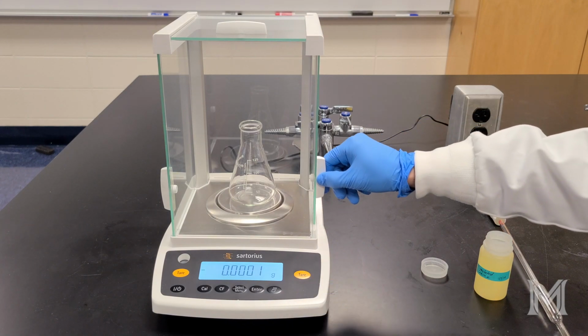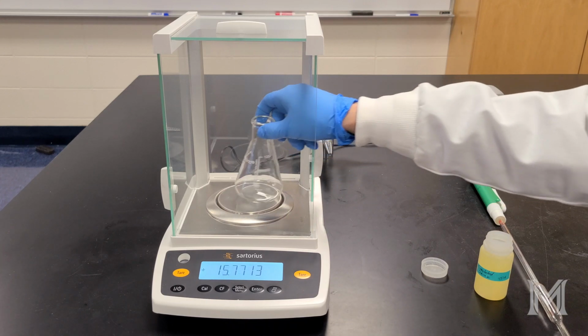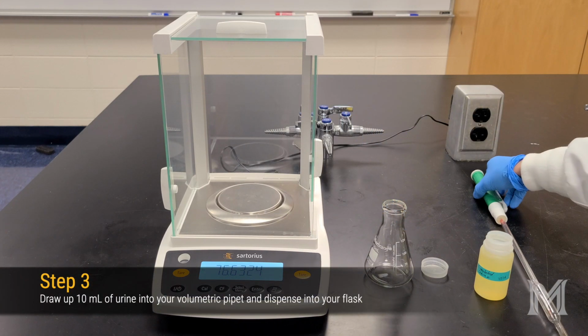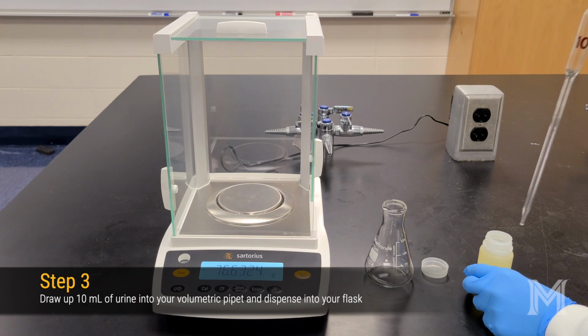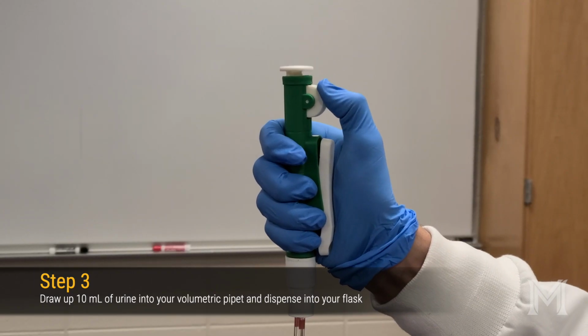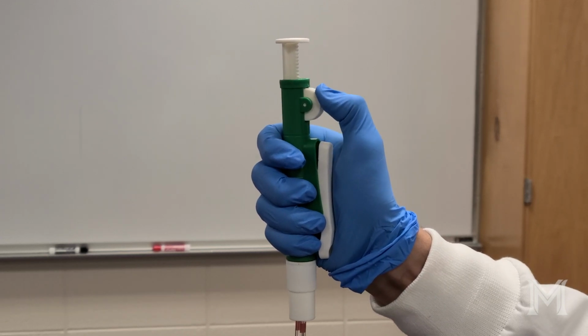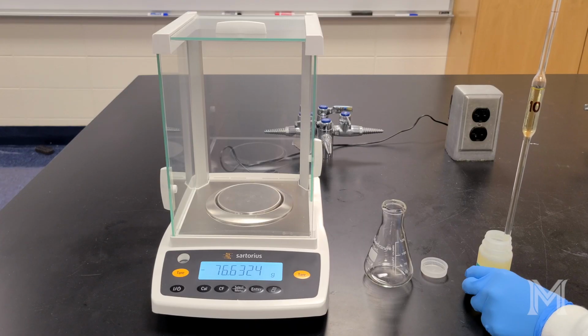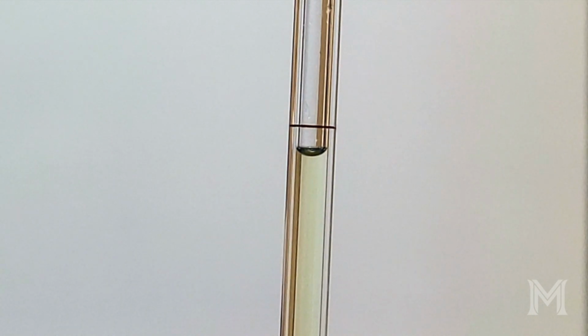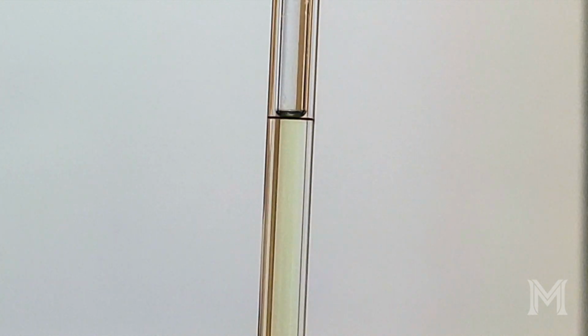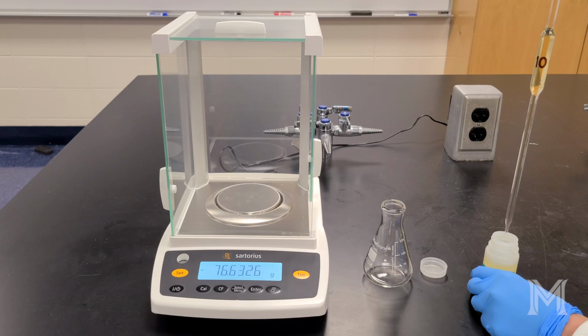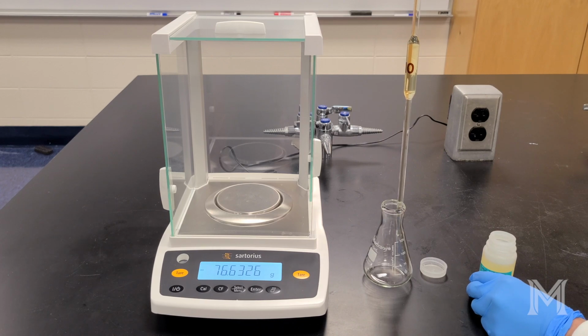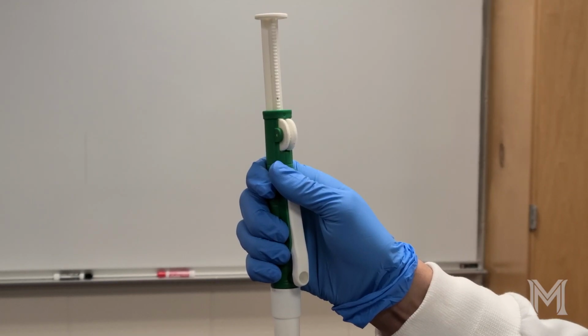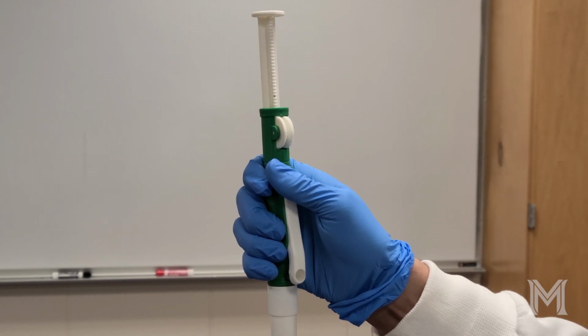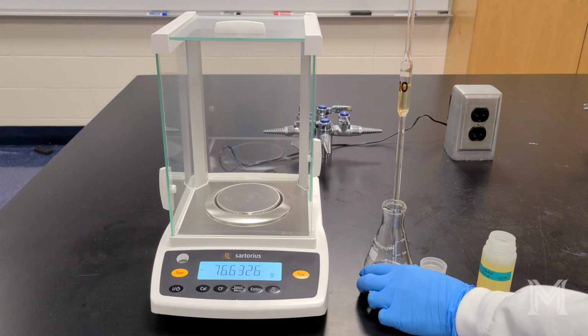Once we've zeroed the reading, remove the flask from the balance, and now we can add our first urine sample to the flask. You're going to use a volumetric pipette, and here you use the pipette pump by rotating the wheel to draw the fluid up into the volumetric pipette. You'll notice that the bulb fills, and we'll draw the liquid up to the calibration line. The bottom of the meniscus should be just touching the line. Make sure that you hold the pipette vertically when reading it, and dispense by pushing in the release lever on the pipette pump. Let the pipette gravity drain and don't try to blow out the tip.